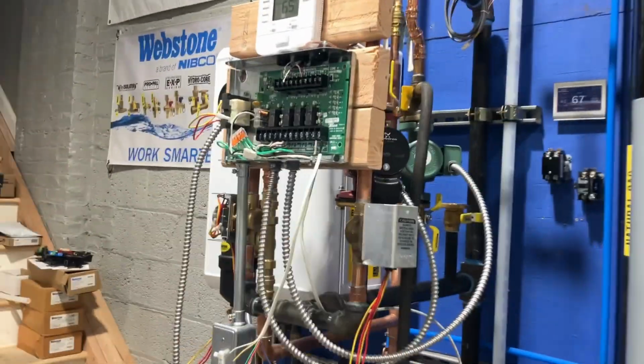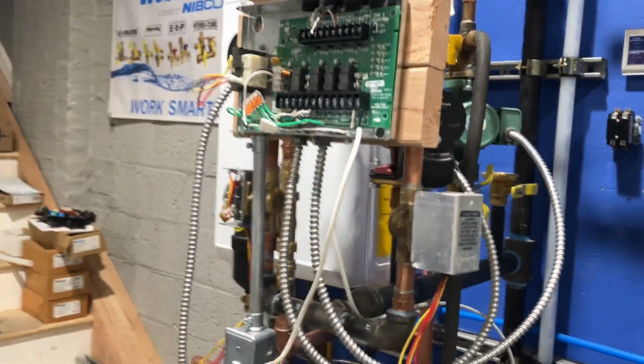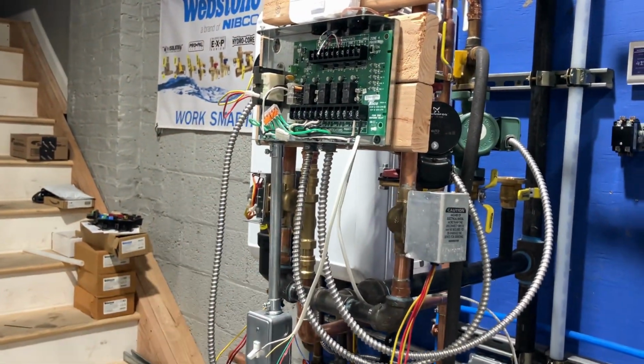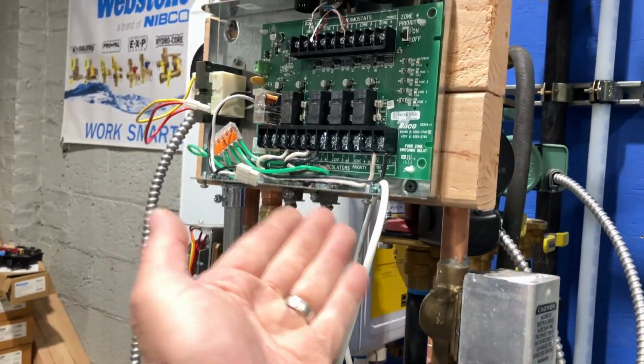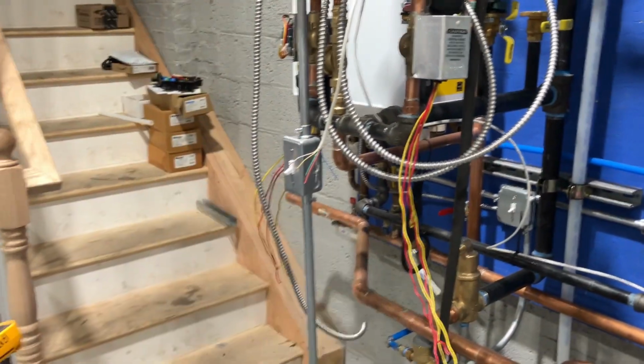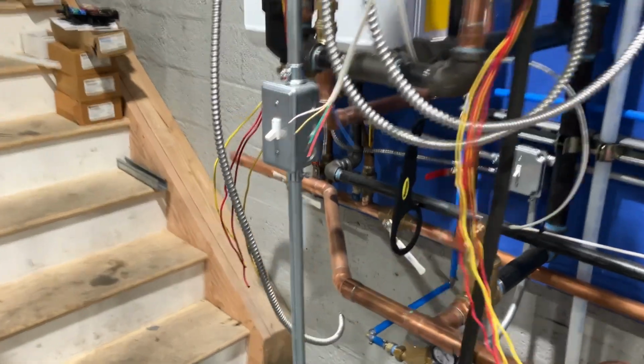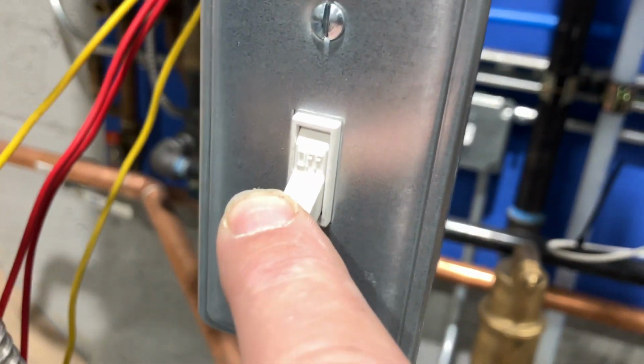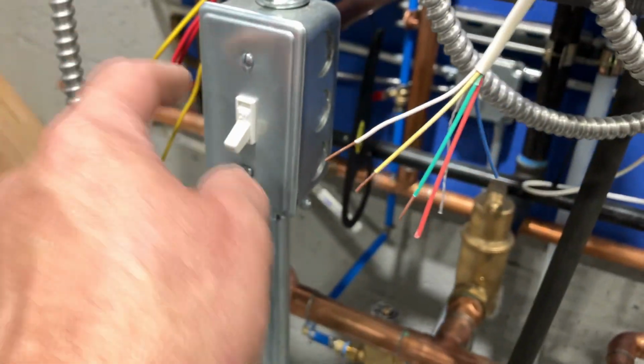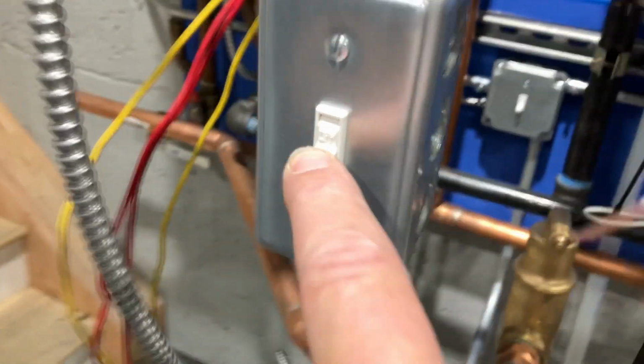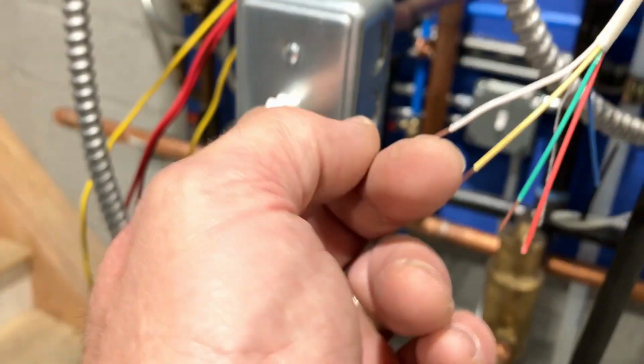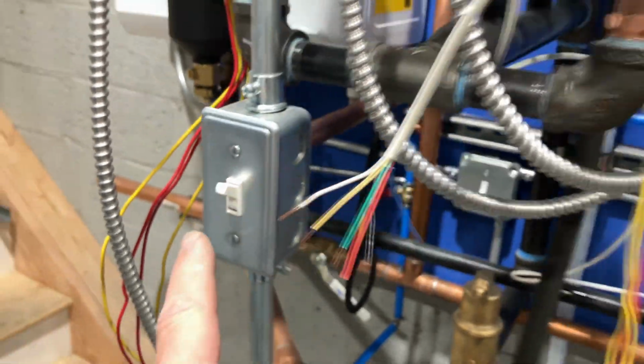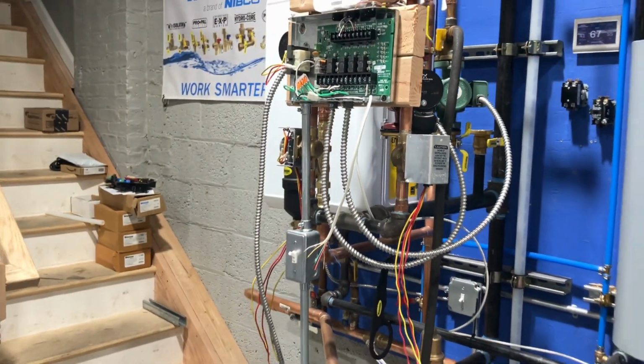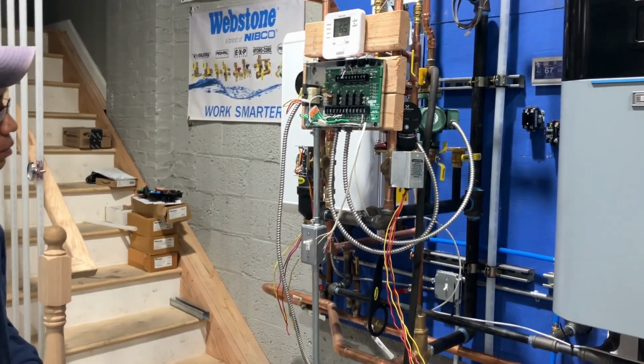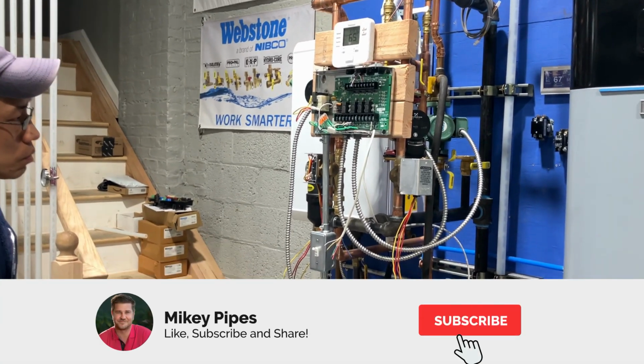So let's say you went to a service call, you go to the boiler, you start getting out your tools, you check for voltage either at the boiler or at the control, you have no voltage there, and then you remember, the switch on top of the stairs is off. Sometimes these electricians or handymen put them in upside down. It could be on, it could be off, but that says off right there. That says on. Always troubleshoot. What I'm trying to stress here is don't just turn switches on without actually troubleshooting and testing first, right?